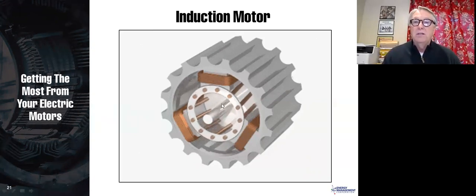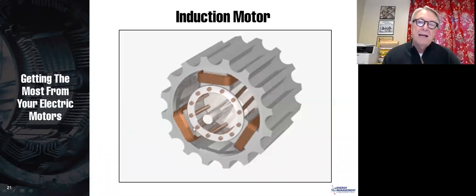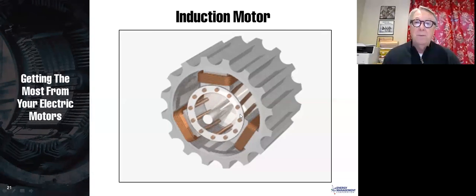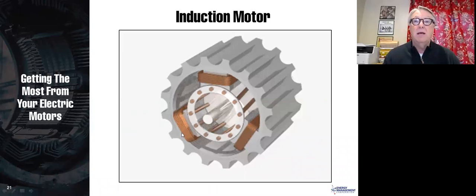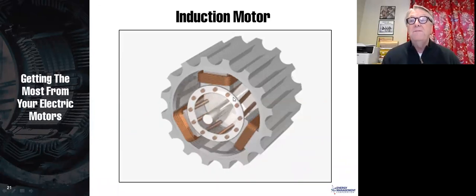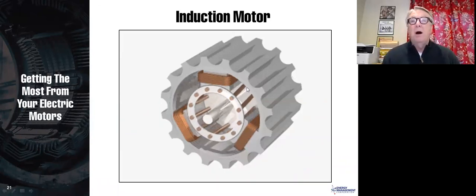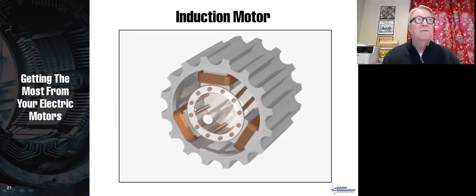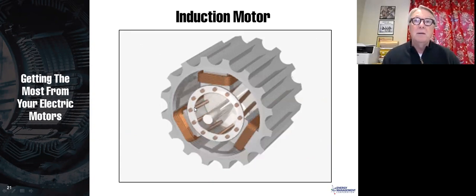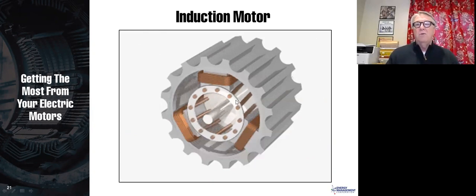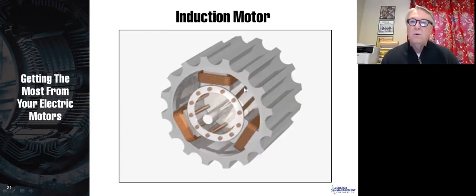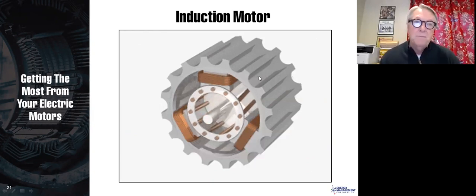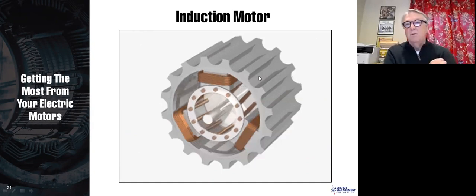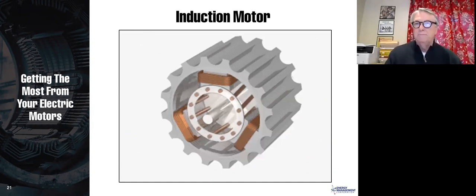And the flux or the magnet in the rotor is going to be going 3,600 RPM because it's going to be going exactly the same speed as the magnet on the stator. But the physical rotor, the bars, the iron, the end rings, the physical rotor is going to slip a little bit. So if you looked at that rotor, you would see the magnet going around this rotor at the slip frequency, which is generally, we'll say, 1, 2, 3%.